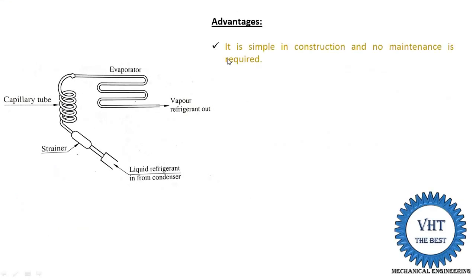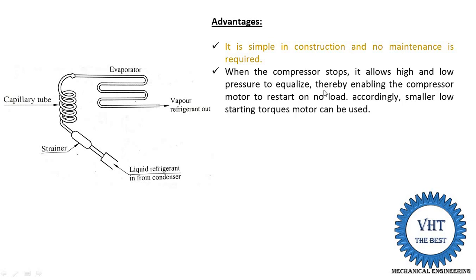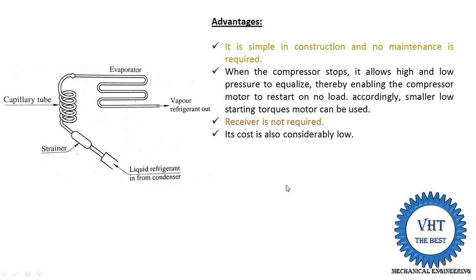The advantages of the capillary tube are: it is simple in construction, no maintenance is required, and its cost is low. When the compressor stops, it allows the high and low pressures to equalize — the high pressure refrigerant in the condenser mixes with the low pressure refrigerant in the evaporator until the same pressure is achieved. Due to this, a smaller low-starting-torque motor can be used in the compressor. Also, a receiver is not required, and the copper tube cost is considerably low.